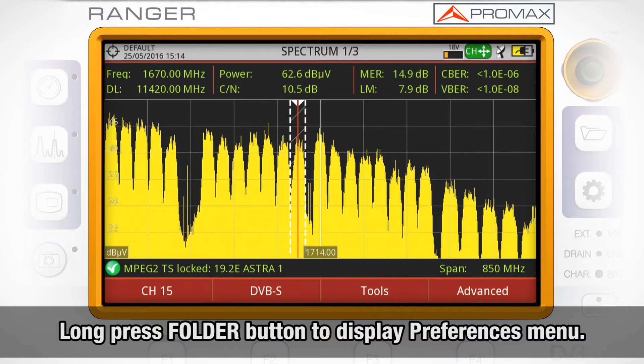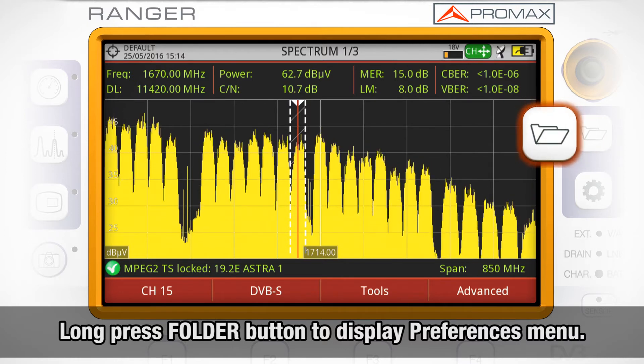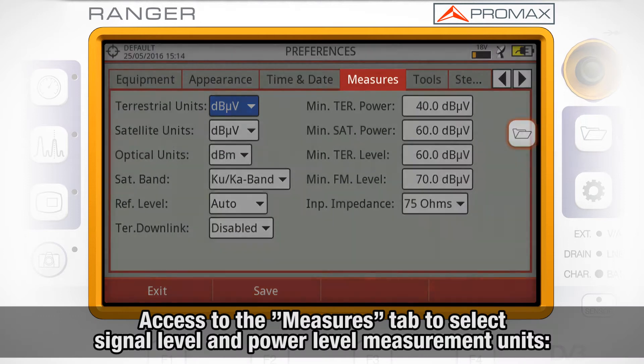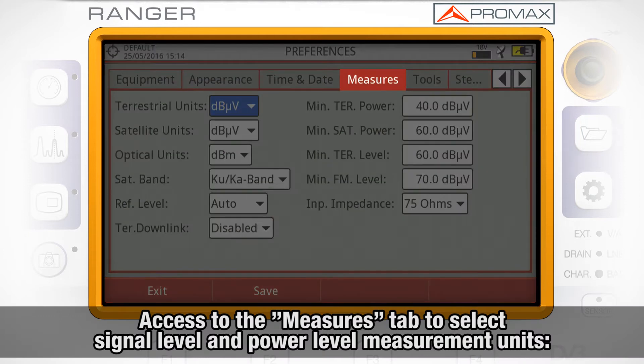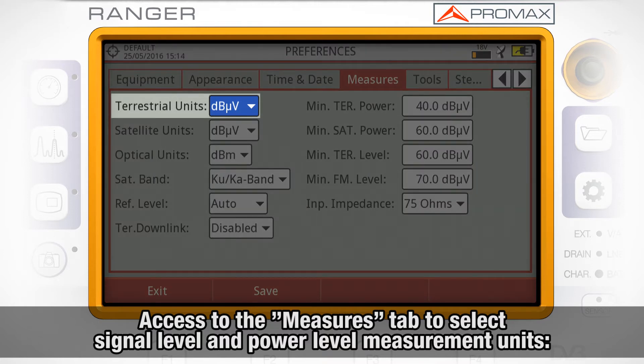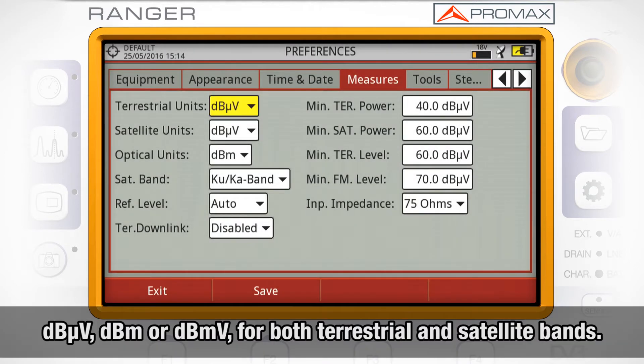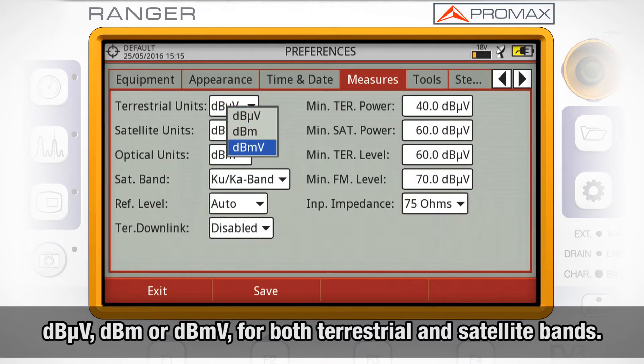If we go to the preferences menu by long pressing the folder button and access the measures tab, here we will be able to select in which units we want the signal level and power level measurements to be displayed. You can choose from dB-micro, dB-m, and dB-millivolt for both terrestrial and satellite bands.